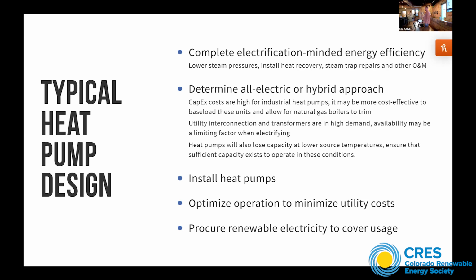There are going to be a couple of challenges. These are early commercialization, so the CapEx is going to be higher for these steam-generating heat pumps. Similarly important, we're seeing limitations on how much utility interconnection you can get — data centers are eating everyone's load interconnection. So if you can't get load interconnection, you might be significantly limited on how big a boiler you can build. And high voltage transformers are also in high demand with very long lead times — if you can get allocated one or two, that might be how big a system you end up building.